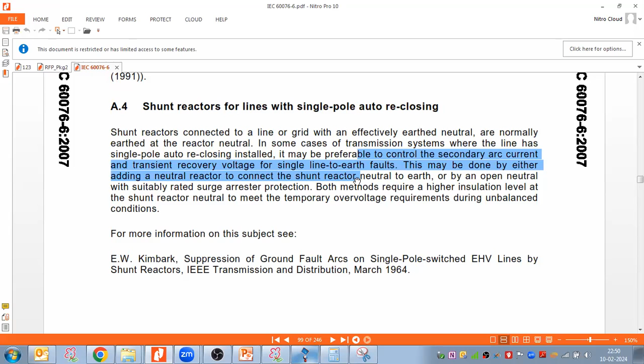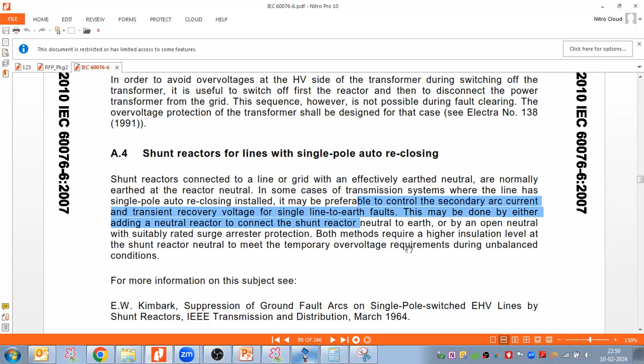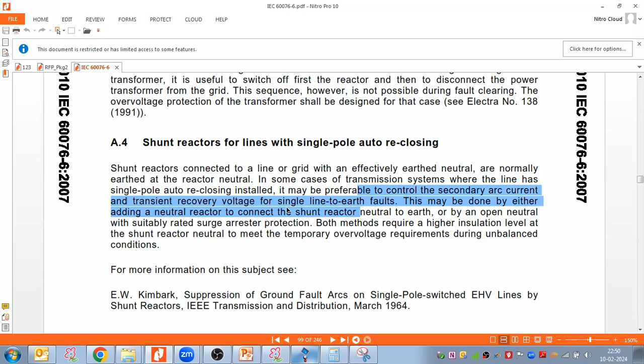So in a system where the line has single pole auto reclosing installed, it may be preferable to control the secondary arc current and transient recovery voltage for single line to earth faults. This may be done either by adding a neutral reactor to connect to the shunt reactor, or by leaving the shunt reactor neutral open to earth with suitably rated surge arrester protections. This is the recommendation coming from this IEC standard. Both methods require a higher insulation level at the shunt reactor neutral to meet the temporary overvoltage requirement during unbalanced conditions. Because you are doing single pole auto reclosing, unbalance will come. This is the IEC standard, which is directly telling you.